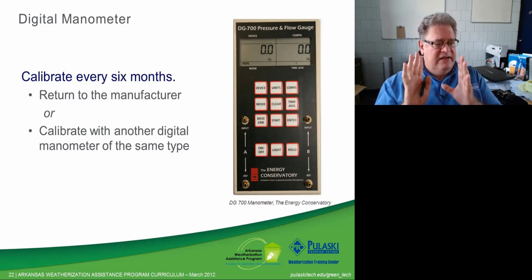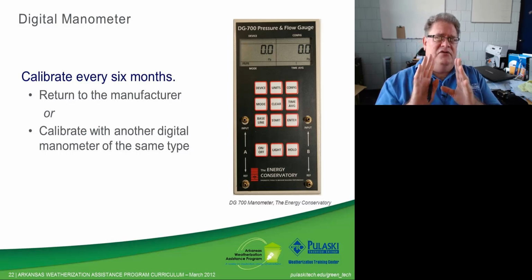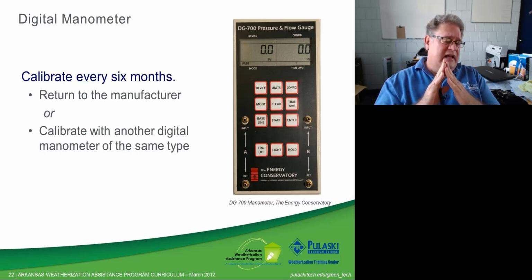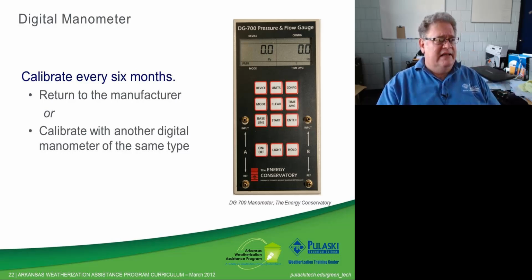It is not the same thing as getting a calibration sticker. It does not do the same function as a true calibration, but what it does is compare 2 manometers and check the delta between them to see how far off they are. If they're very, very close to the same, within tenths of a Pascal, I wouldn't worry about it. When they get a little bit more than that, then you need to get to it. I think I will have a copy of that field calibration procedure available up on the LMS, up on Blackboard.